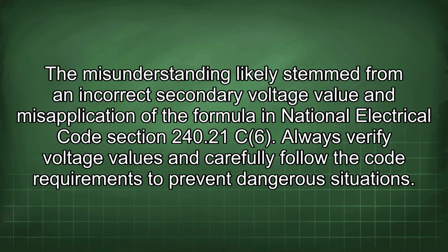The misunderstanding likely stemmed from an incorrect secondary voltage value and misapplication of the formula in National Electrical Code Section 240.21(C)(6). Always verify voltage values and carefully follow the code requirements to prevent dangerous situations.